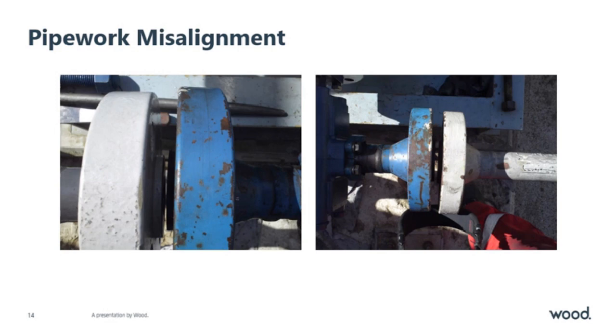That's one important point. The system never brought production to a stop because the pumps are in duty standby mode. However, the MTBF was about 1300 hours, so once a pump failed, it became a race to get it swapped out and available, just in case that standby pump had also started to fail in quick succession.